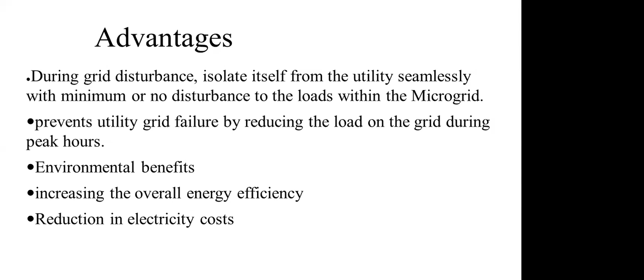The microgrid has advantages, but we have a lot of challenges also. Voltage has to be properly maintained, especially when there is a grid failure. That means you need to maintain voltage and frequency. If the grid is there, these two are not issues, because the grid supplies the reference voltage and frequency. If the grid fails, then you need to generate a proper voltage and frequency reference, and maintain power quality. Because you have a combination of sources and controls, power quality also comes in, and all the demands have to be met within the standards. That means 3% of current harmonics and 5% of voltage harmonics, and the voltage limits also have to be met within the standard. IEEE has a standard for this, with the upper and lower limits.